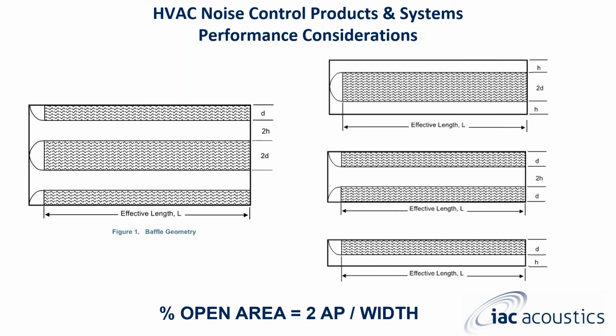Now, another performance consideration is this. Next, we have the percent of open area. This is calculated as AP divided by width. Now, note here that half the gaps and half baffle thicknesses are H and D respectively, and performance is only based on these parameters. So, take a look at the single silencer on the left, then look at the 3 on the right, having different configurations. All have the same acoustical performance as the one on the left, basically assuming that the dimensions for H and D and L are the same.